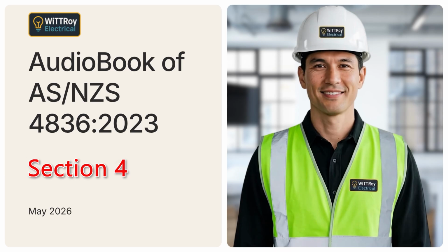Section 4. Risk Control for Specific Situations. Today we're moving into Section 4 of ASNZS 4836. This section is about risk control for specific work situations. Different hazards create different kinds of risk, so the control measures must match the real situation in front of you. Working near exposed, energized parts is different from working near batteries. Working around capacitors is different from working in a hazardous area. Working in a cramped ceiling space is different from working in a clear switch room. So before work starts, look at the equipment, the environment, stored energy, building materials, earthed situations, and anything else that may affect the safety of the job.